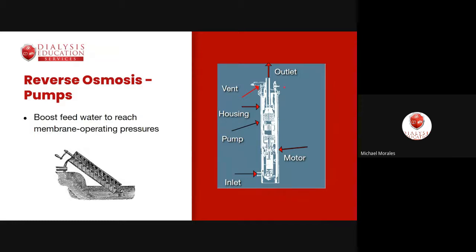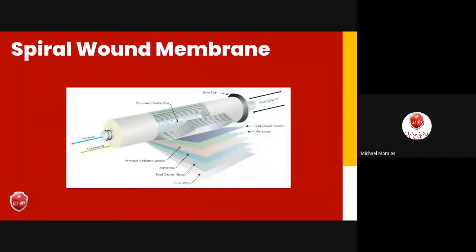The RO membrane requires booster pumps to build up high pressure. Water is forced across multiple layers of membrane — a jelly-roll configuration — from the outside of a tube-shaped filter to the inside, where a perforated tube carries product water (permeate) to the machines. If water doesn't make it through, it becomes concentrated. Temperature affects how much water makes it through to become product water.